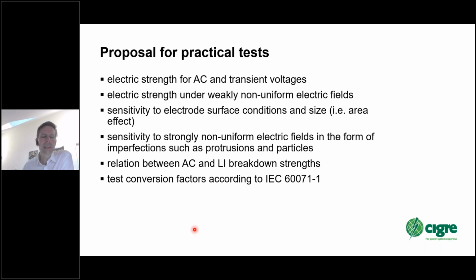The practical tests covered several factors: electric strength for AC and transient voltages across varying degrees of field uniformity, from weakly to strongly non-uniform fields; sensitivity to electrode surface conditions like roughness and area effects under strongly non-uniform configurations; sensitivity to AC versus lightning impulse; and the ratio between AC and LI breakdown strength, i.e., test conversion factors standardized in IEC standards.